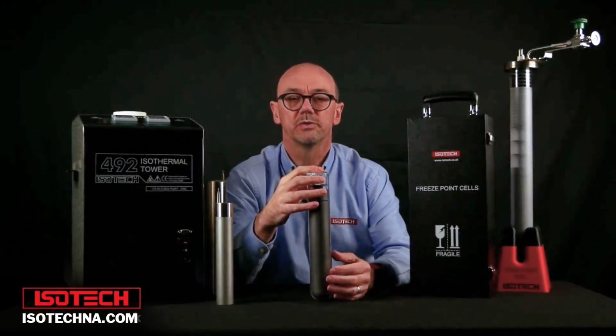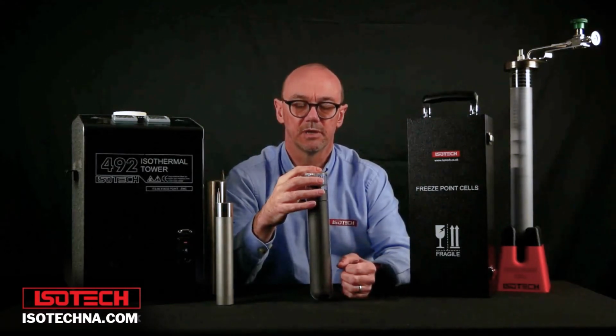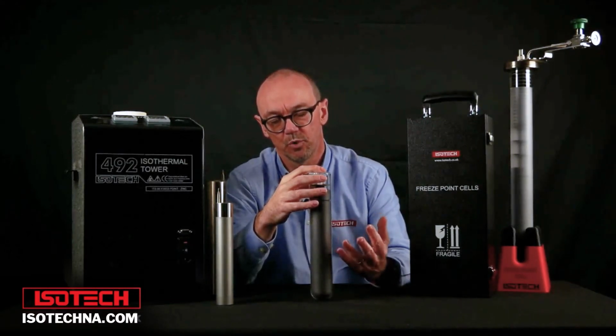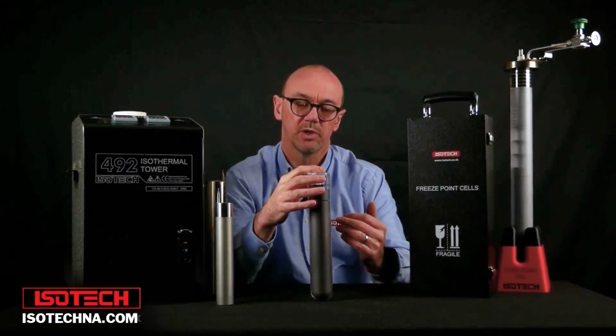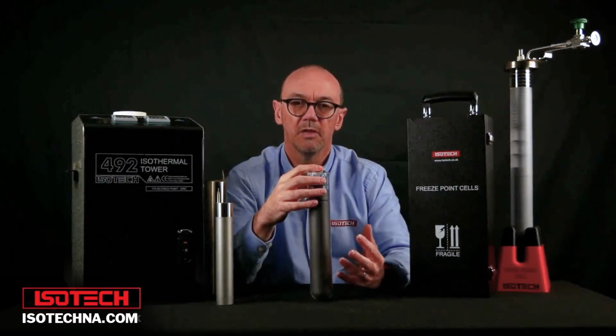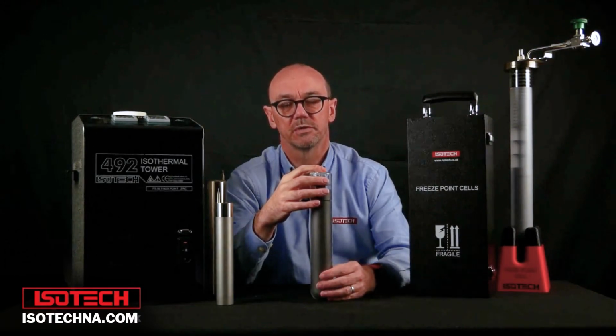So a common question is, if we've got an ITS-90 fixed point cell, and the temperature comes from the purity of the metal, and if we know the pressure, we can be very confident in that temperature, then does the cell need a calibration certificate?